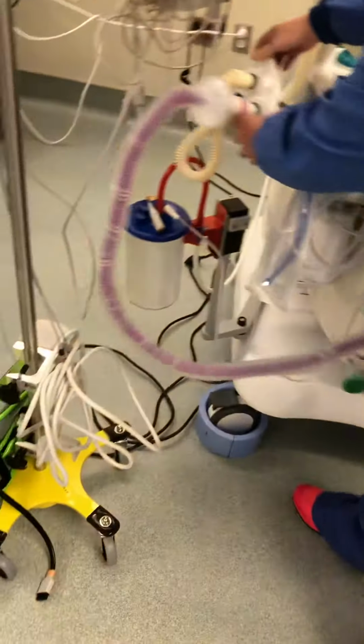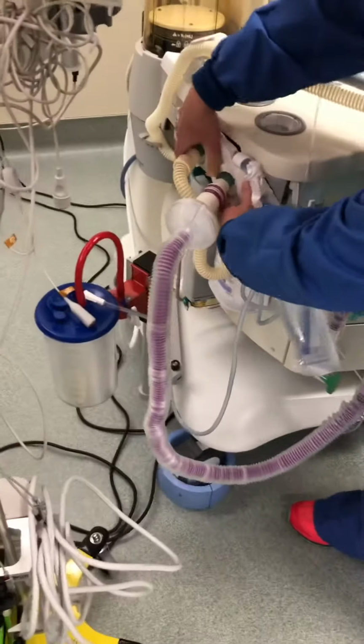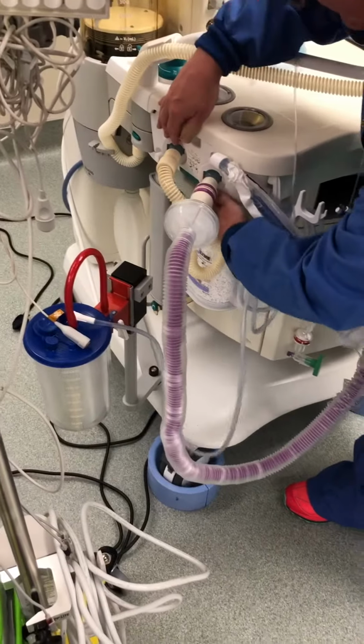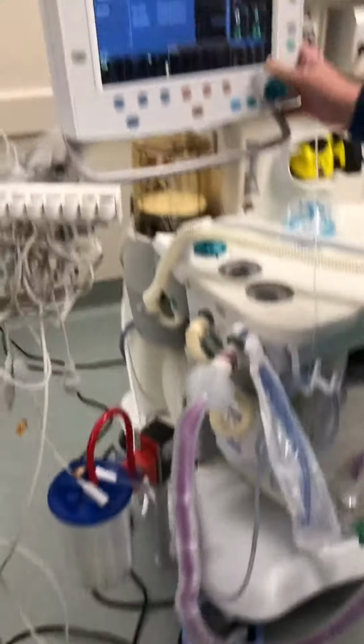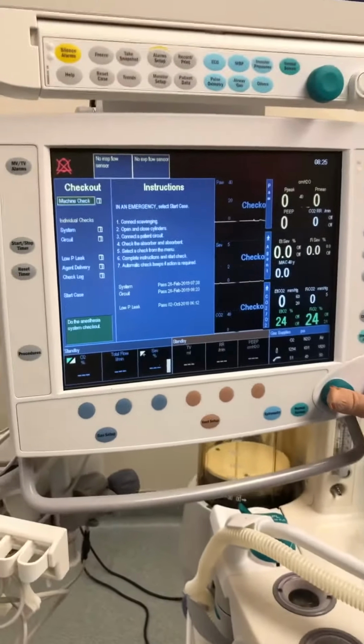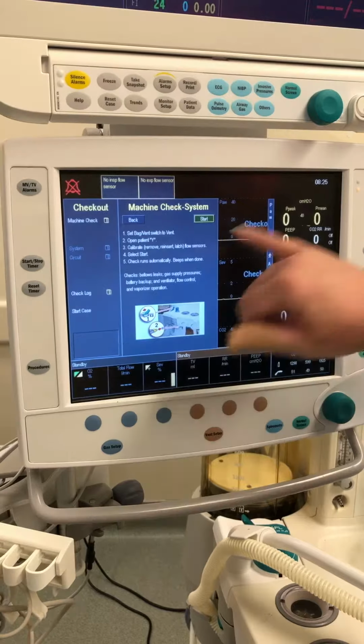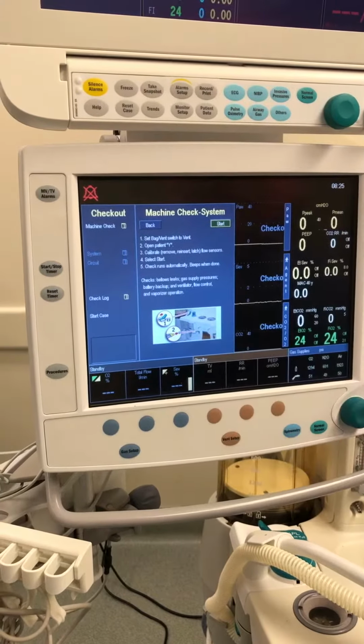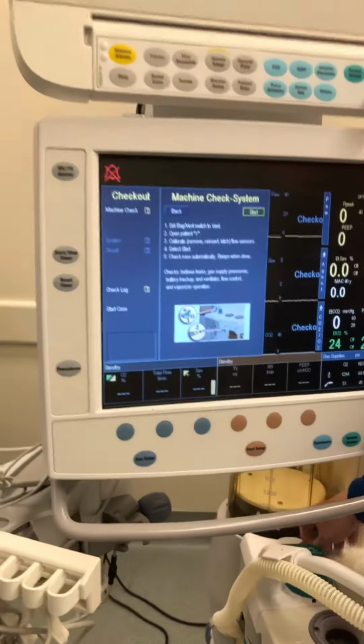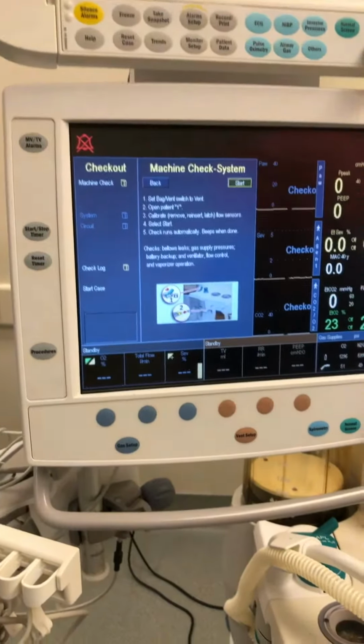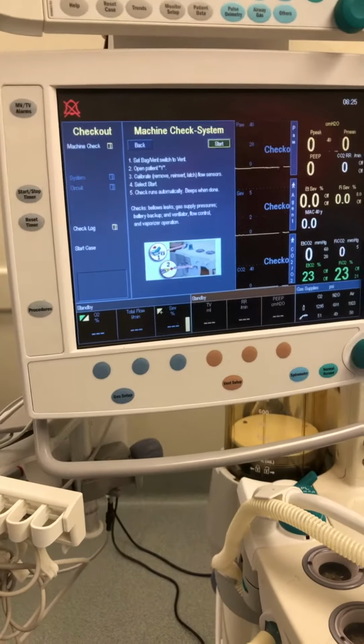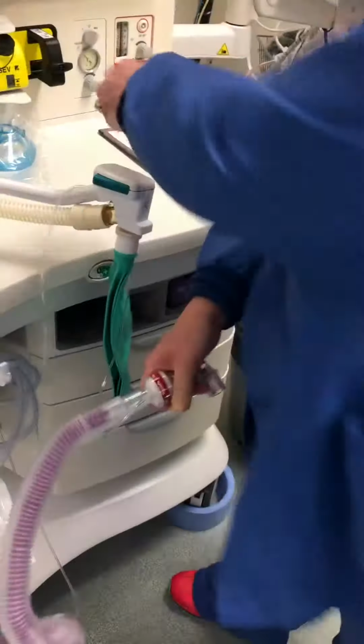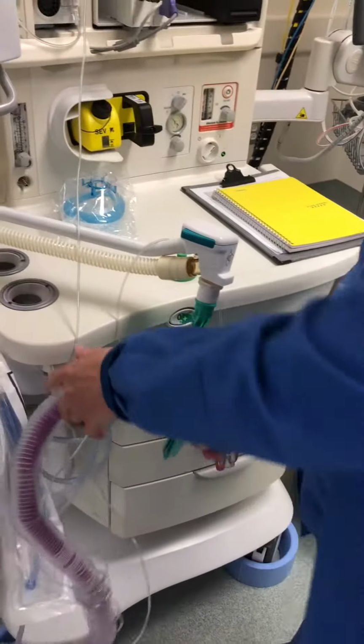So I'm going to put the flow sensor module back in here. And a lot of times what I'll do is go back and do the machine check. You just want to follow the instructions, your picture's down below. So back to vent, switch to vent, open the patient Y, which they use the green plug to occlude, which is completely fine.